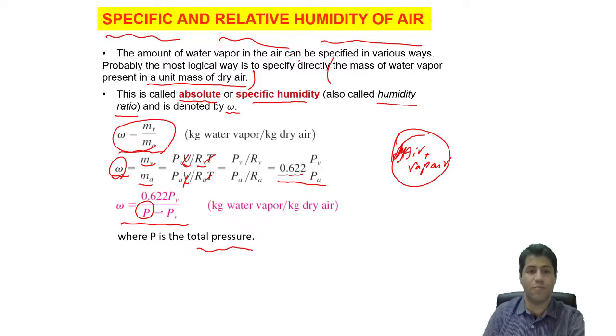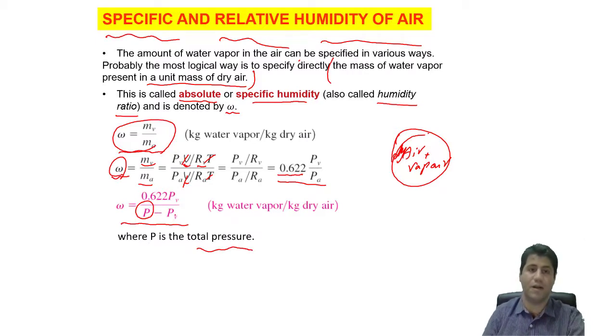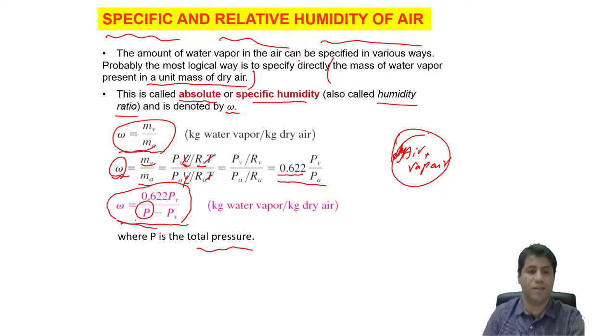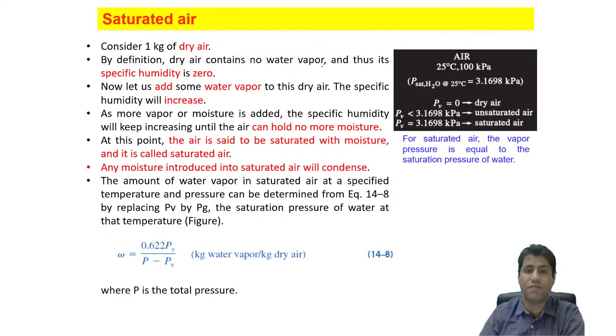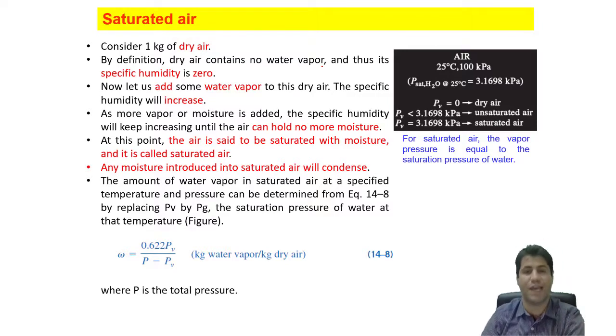This second equation — ω = 0.622·Pv/(P − Pv) — is more common in calculations of specific humidity, and later we will see why. So this is the equation we use to calculate the absolute or specific humidity of atmospheric air.